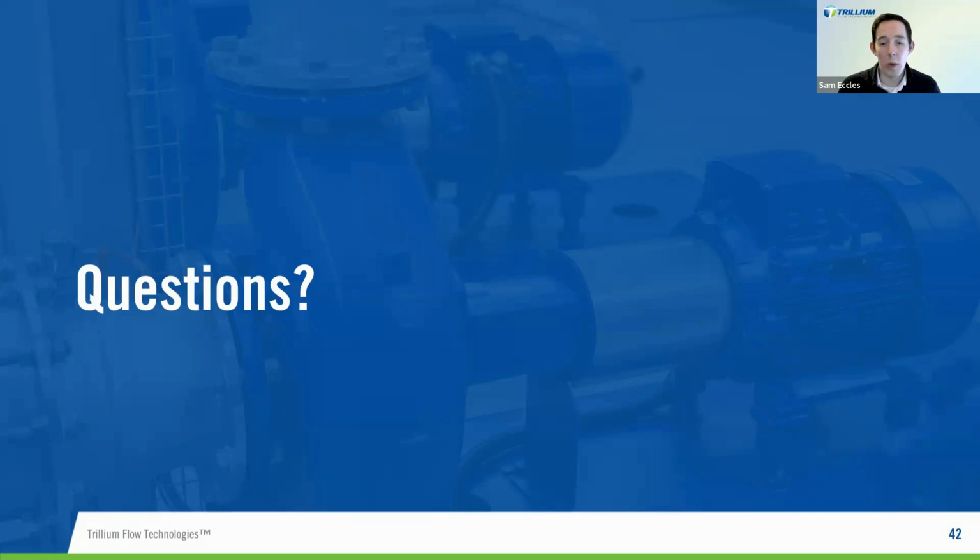Yeah, so assuming that's speed, the answer is yes. And exactly what that lowest point will be will depend. Okay, yes, thank you for clarifying, Samuel. So yes, you just come back in terms of speed. Short answer is yes. The detailed answer, again, is it depends, but it depends on exactly which equipment we're talking about, which VFD. There will be limits to how much turn down, so how slowly you can run the VFD, based on the VFD and motor manufacturer.